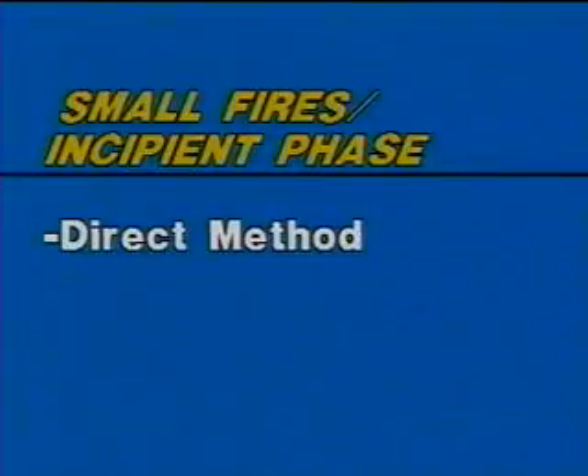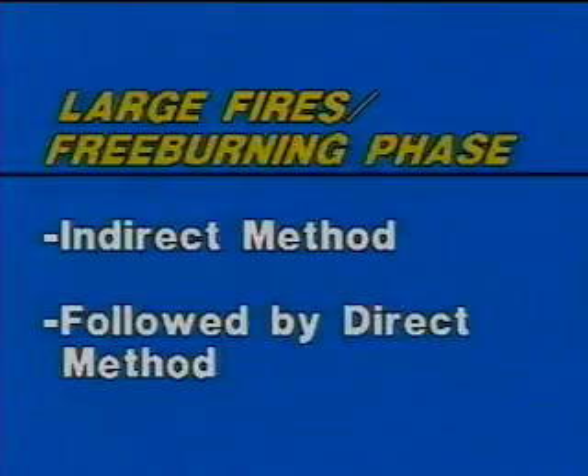So, on small fires, those in the incipient phase of burning, the direct method of firefighting is used. With the free burning phase, the indirect method is used first, followed by the direct method, using as little water as possible. And of course, overhaul the area for any hidden fire.